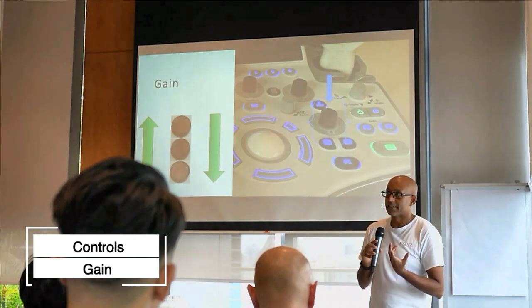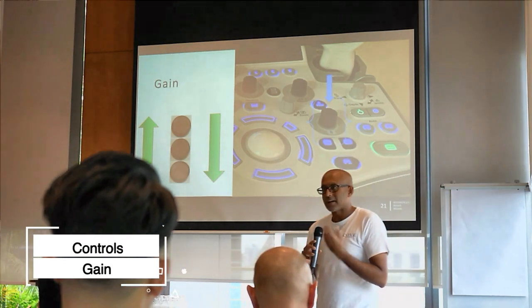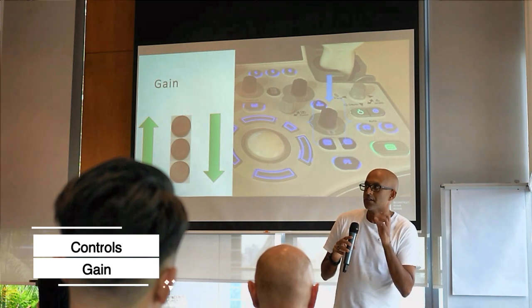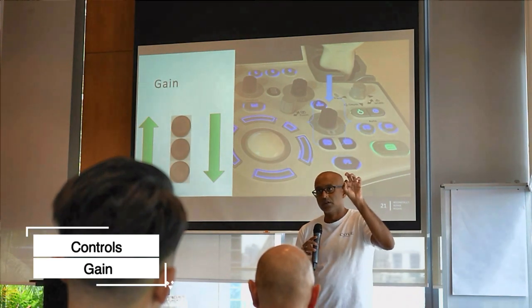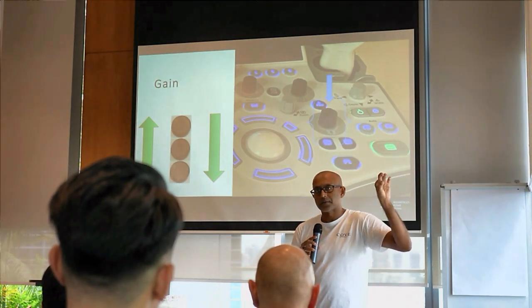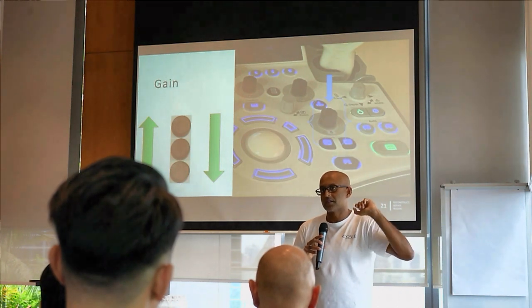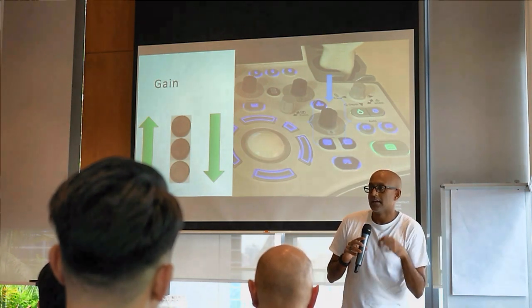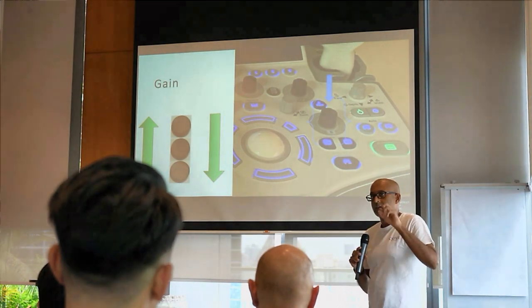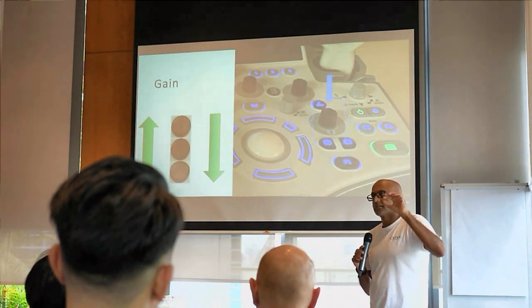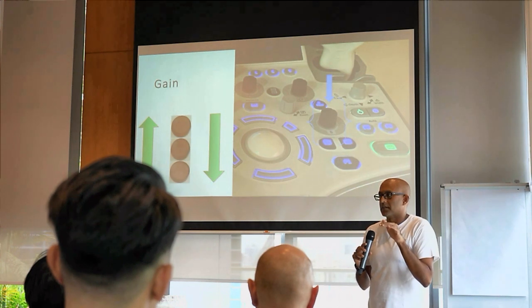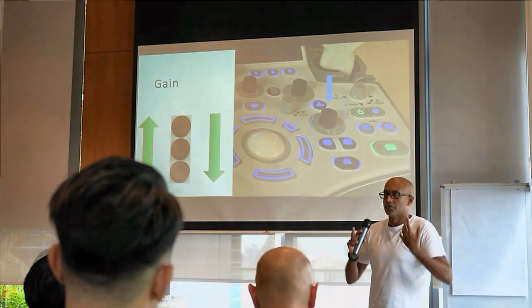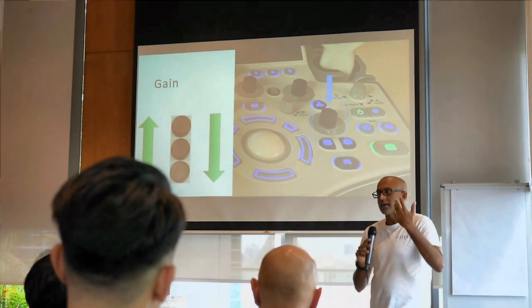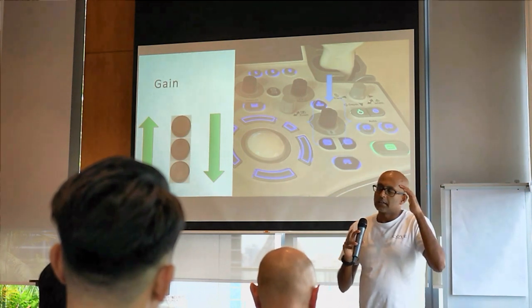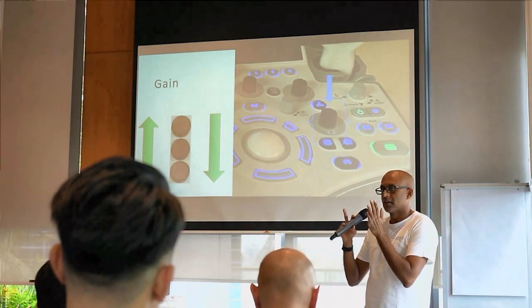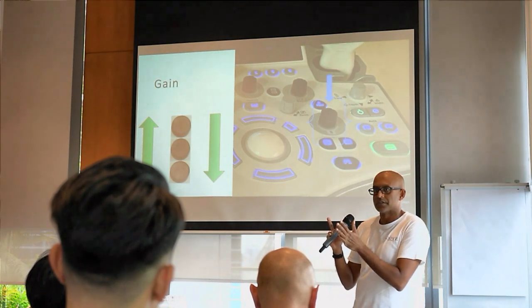Another one, your gain. Gain is basically like the aperture on a camera. Okay? So if the gain is very small or low, then the aperture is going to be very small and you're not going to get much sound waves back. If you increase the gain, the aperture gets bigger and you get lots and lots of sound waves back. But what's the issue with that? You get a lot more noise. Okay? So you have to find a balance between getting a sharp image and minimizing the amount of noise you get.